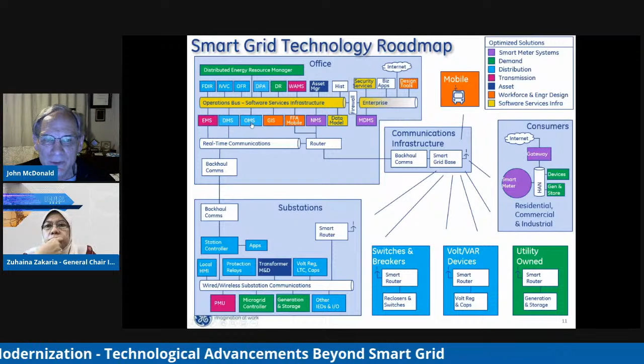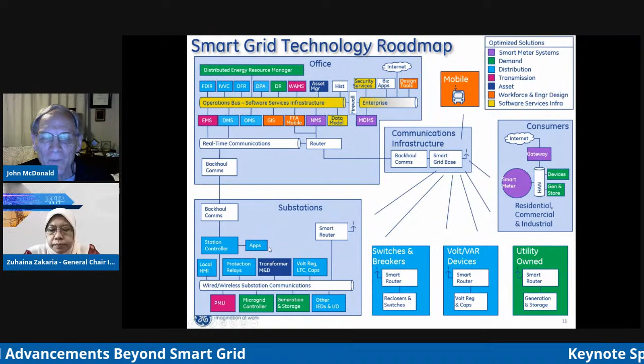Going down to the substation level, we have the station controller, showing applications at the substation level. What we mean is we take FDIR, fault detection, isolation, restoration, and integrated VoltVAR control, and not only run these centrally on the DMS, but also distribute them down at the substation level, where we've been running them as well.